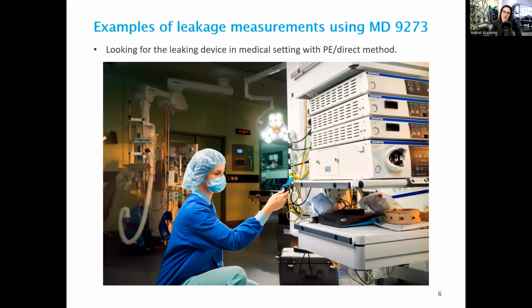So here we have our first example of using leakage current measurements for troubleshooting. This is a medical location. Typically, the surgery room is going to have an IT grounding system, which means that it is isolated from the common ground of the hospital. This allows the system within the surgery to have higher availability. In case of an insulation break, the system is going to remain safe and functional, but it will typically start functioning like a TN grounding. In hospital settings, where patient safety is of utmost priority, there are often additional RCDs to ensure safety in case of a second failure. Now, the main Metrel instrument to be used in this environment is the MI3110.